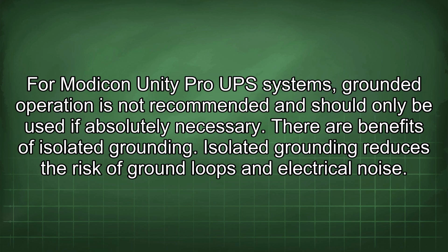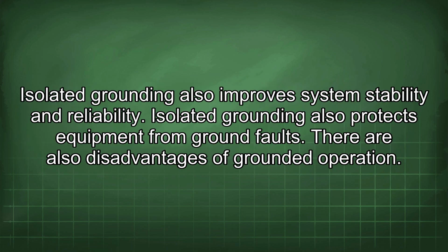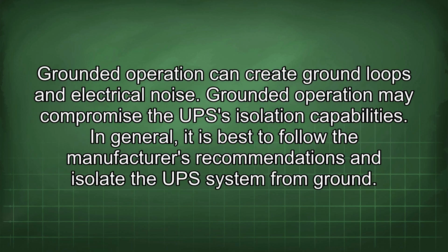There are benefits of isolated grounding. Isolated grounding reduces the risk of ground loops and electrical noise. Isolated grounding also improves system stability and reliability. Isolated grounding also protects equipment from ground faults. There are also disadvantages of grounded operation. Grounded operation can create ground loops and electrical noise. Grounded operation may compromise the UPS isolation capabilities. In general, it is best to follow the manufacturer's recommendations and isolate the UPS system from ground.